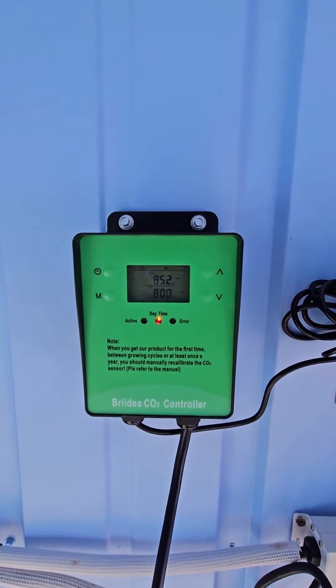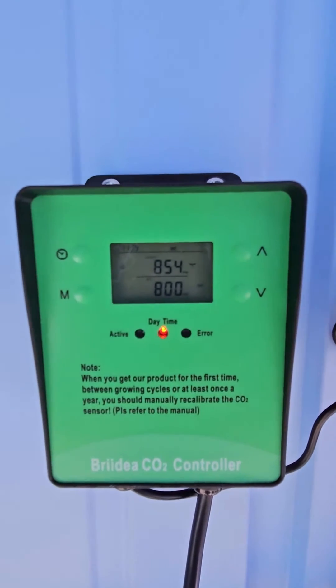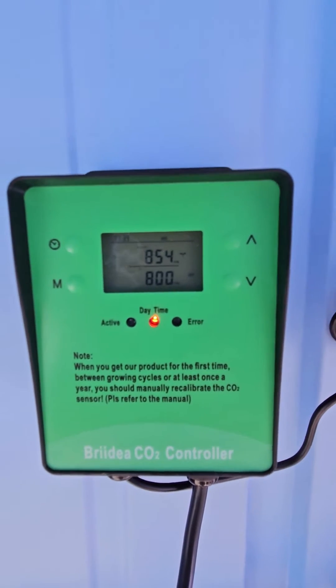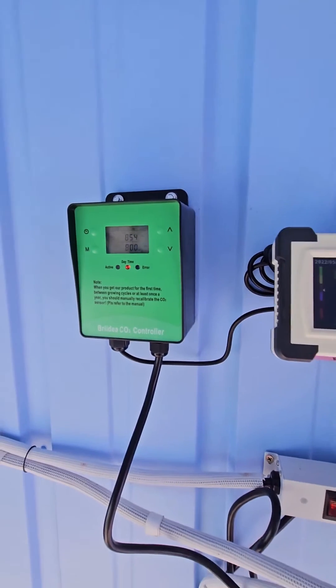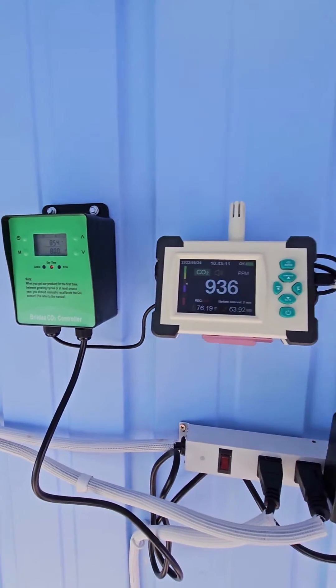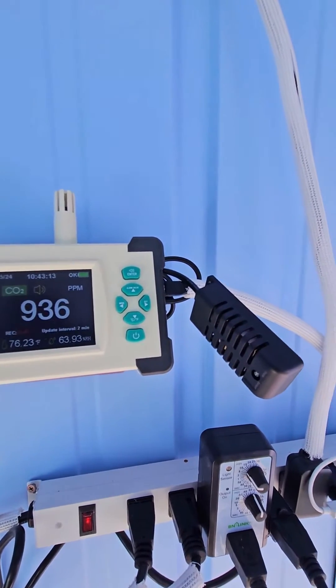So this is the controller - this is what's telling my regulator to turn on and off based on parts per million. Right now just to get things calibrated, I've got it set to 800 PPM and then it's got a 50 PPM dead band, meaning it can swing 50 parts per million before it'll start activating again. That just keeps it from cycling.